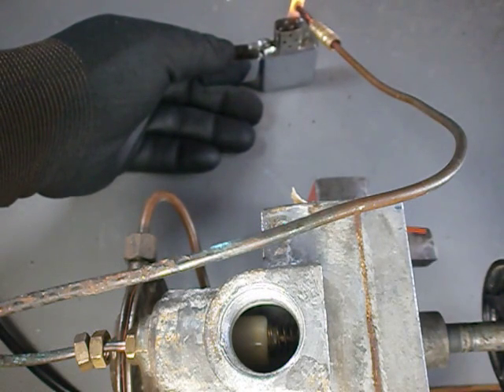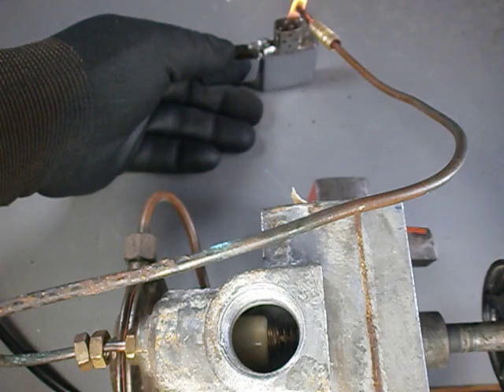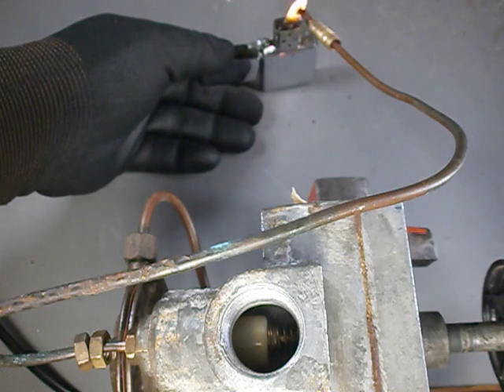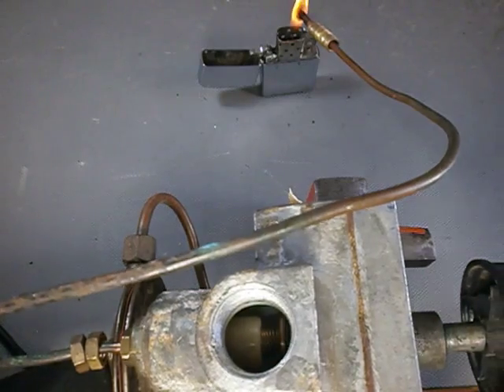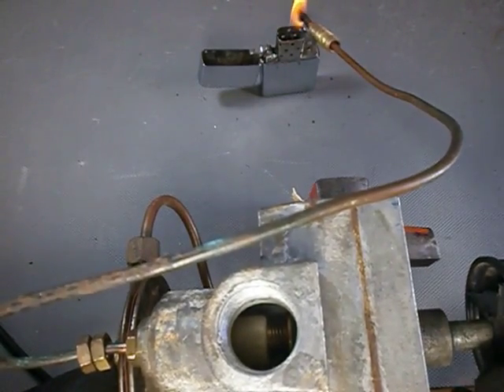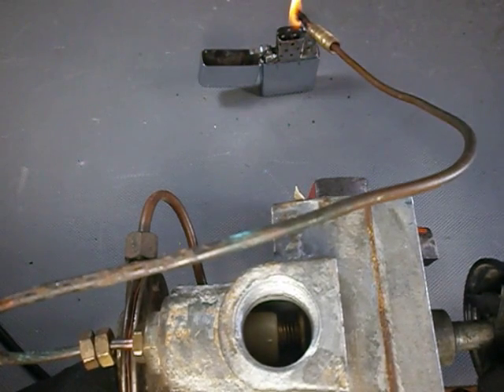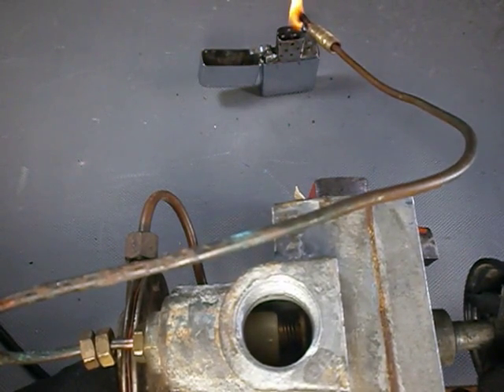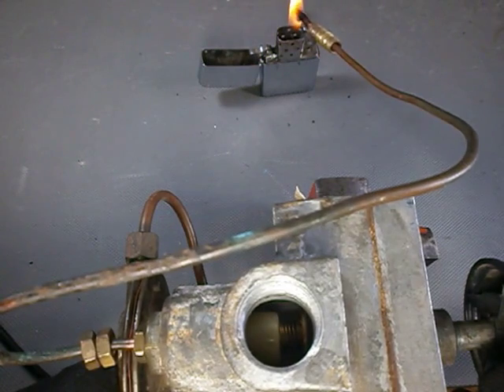This because the current generated by the thermocouple is not enough to attract the valve shaft which is away from the electromagnet. Now if we press the reset button, we open the valve and get it close to the electromagnet. If we now hold it while the thermocouple is being heated up by the pilot light, we can release it and the valve stays open by action of the electromagnet.